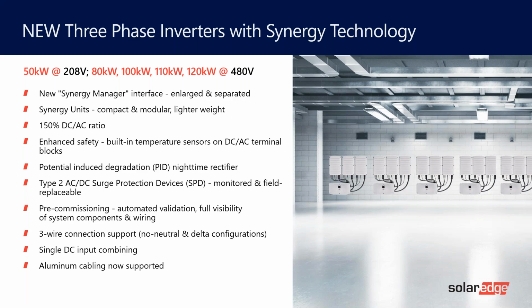So that Synergy unit now has built into it a PID, or potential induced degradation, nighttime rectifier. What that means is, if you have concerns of modules building up PID during the day, which is quite common on commercial applications, the PID rectifier reverses polarity at night, so it reverses that negative impact on the modules. So that's included, no extra cost for that.